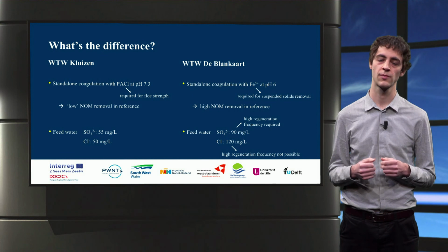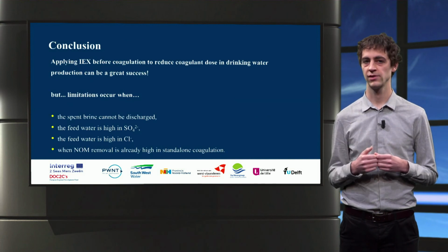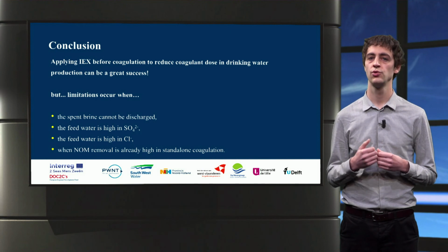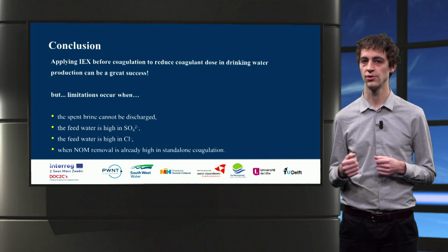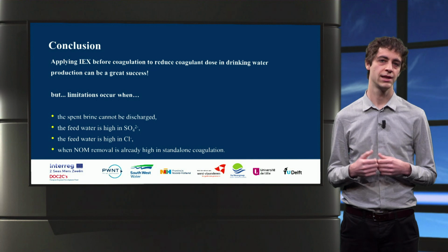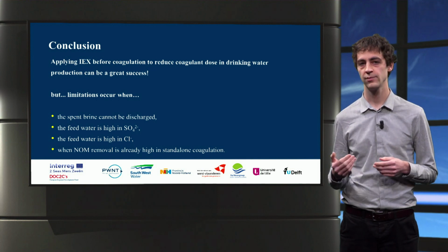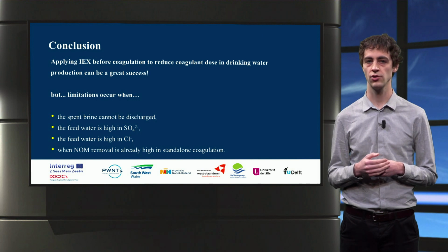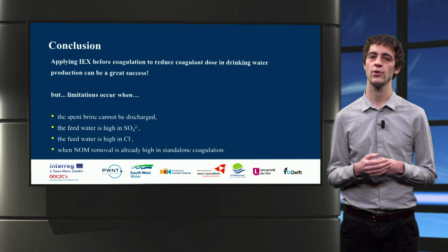Concluding this presentation, applying ion exchange before coagulation to reduce the coagulant dose can be a great success. However, limitations occur when the spent brine cannot be discharged, when the feed water is high in sulfate and chloride, and when NOM removal is already high in standalone coagulation.